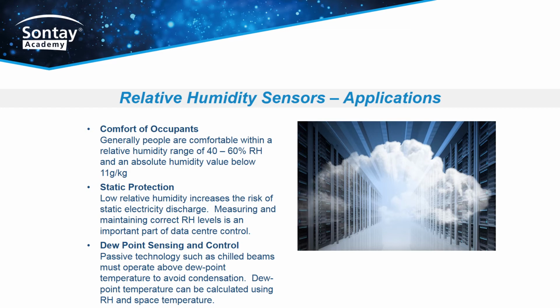Another important use of relative humidity sensors is in the calculation of the current dew point temperature. Dew point temperature is the temperature at which condensation will start to form on surfaces, based on the air temperature and moisture content. Preventing passive cooling devices such as chilled beams and chilled ceilings from falling below dew point is important, as these cooling systems have no means of collecting condensate and directing it into a drain.